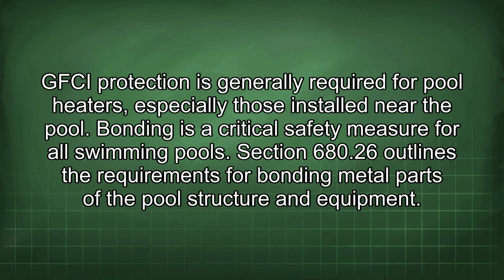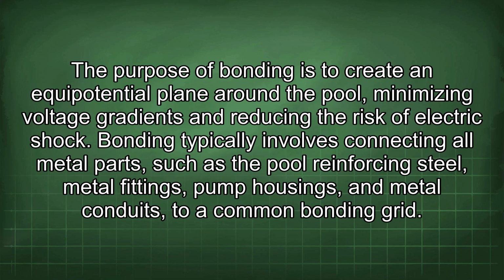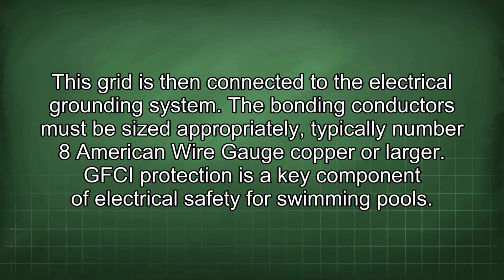Bonding is a critical safety measure for all swimming pools. Section 680.26 outlines the requirements for bonding metal parts of the pool structure and equipment. The purpose of bonding is to create an equipotential plane around the pool, minimizing voltage gradients and reducing the risk of electric shock. Bonding typically involves connecting all metal parts, such as the pool reinforcing steel, metal fittings, pump housings, and metal conduits, to a common bonding grid. This grid is then connected to the electrical grounding system. The bonding conductors must be sized appropriately, typically number 8 American wire gauge copper or larger.